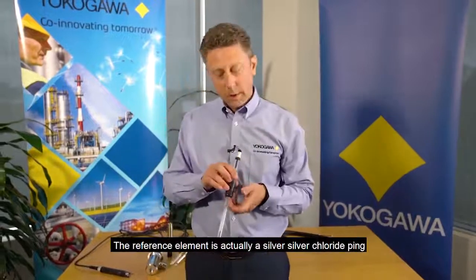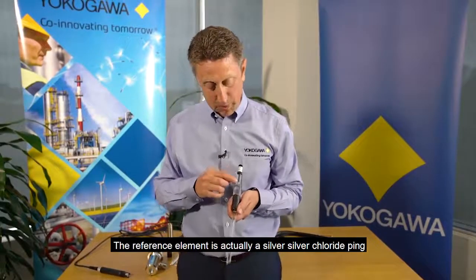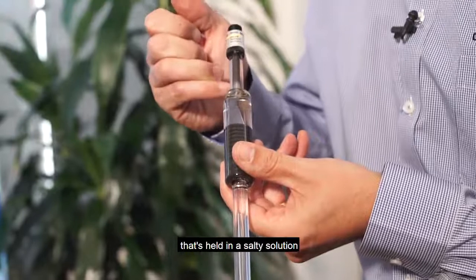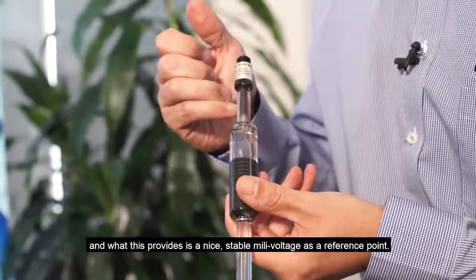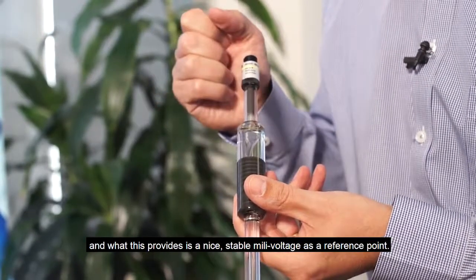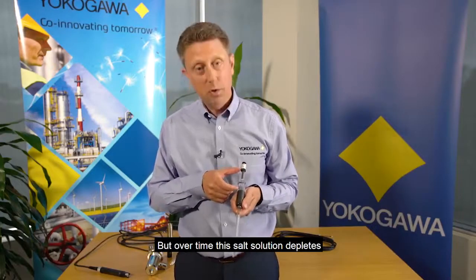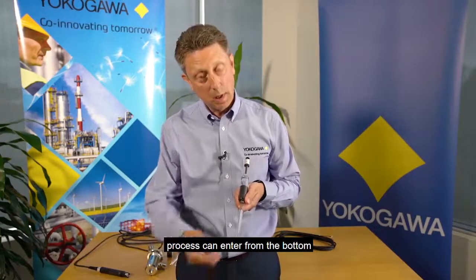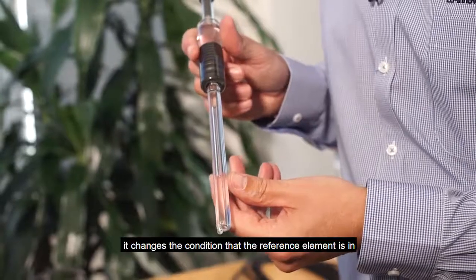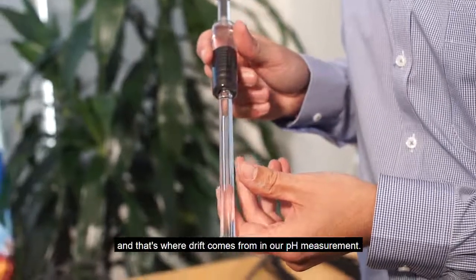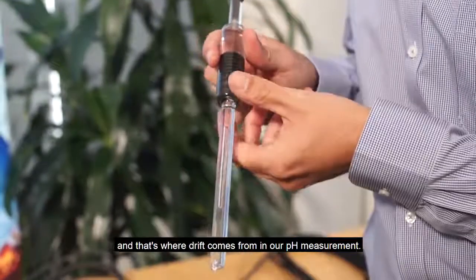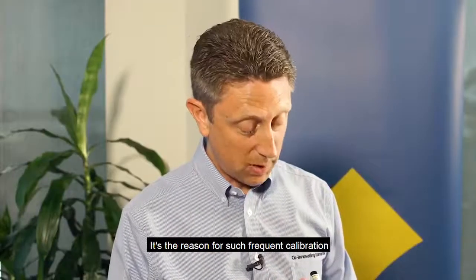A reference element is actually a silver silver chloride pin held in a salty solution, which provides a nice stable millivoltage as a reference point. But over time this salt solution depletes, process can enter from the bottom, and it changes the condition the reference element is in. That's where drift comes from in our pH measurement, and it's the reason for such frequent calibration.